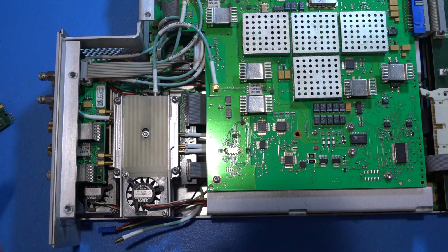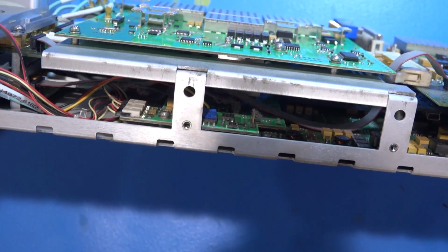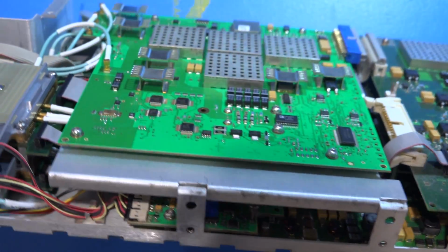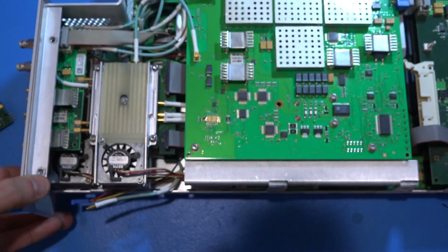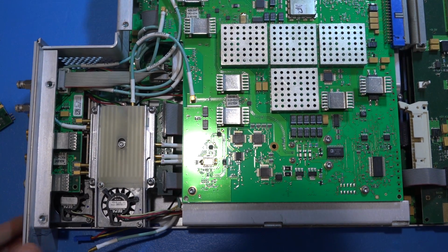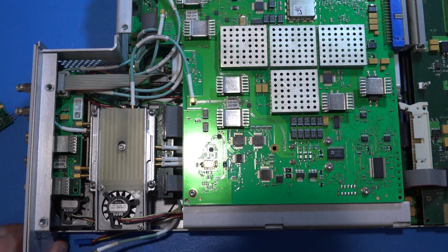Unfortunately, you have to kind of completely close this back up before you can put it in, because it's got a railing on each side which is needed to guide it into place. And the other thing I also noticed is that this thing was filthy, and it still has absolutely tons of dust in it, which means that I'm going to have to remove the other module, the error detector module, and clean that too if I want to extend the life of this instrument. Hopefully we can fix it, or if we can at least do something about the problem we are seeing.